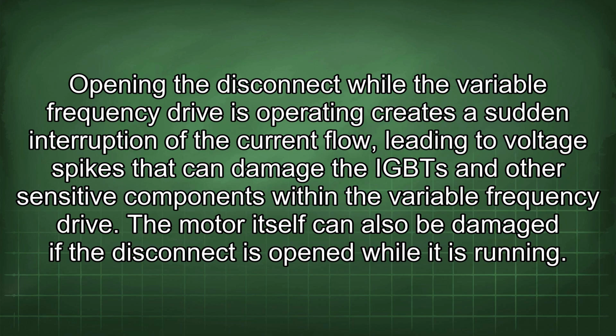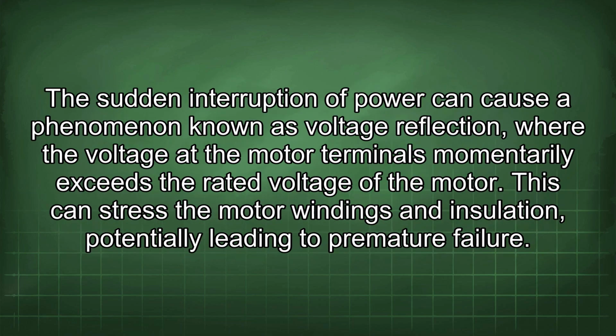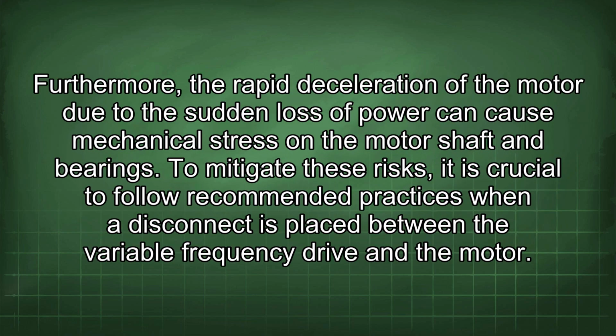The motor itself can also be damaged if the disconnect is opened while it is running. The sudden interruption of power can cause a phenomenon known as voltage reflection, where the voltage at the motor terminals momentarily exceeds the rated voltage of the motor. This can stress the motor windings and insulation, potentially leading to premature failure. Furthermore, the rapid deceleration of the motor due to the sudden loss of power can cause mechanical stress on the motor shaft and bearings. To mitigate these risks, it is crucial to follow recommended practices when a disconnect is placed between the variable frequency drive and the motor.